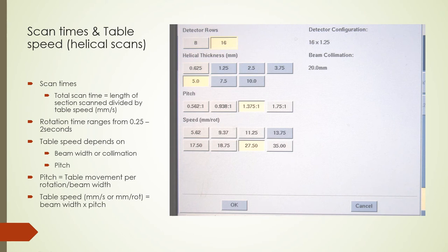For example, with a 40 mm beam width scanning a 200 mm section, a pitch of 1.25 and 1-second rotation time gives a table speed of 40 mm times 1.25, equaling 50 mm per second. Scanning 200 mm at 50 mm per second yields a scan time of 4 seconds. Using a pitch greater than one speeds up a scan; a pitch less than one slows it down.